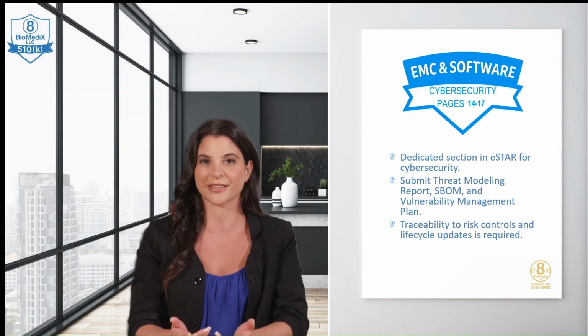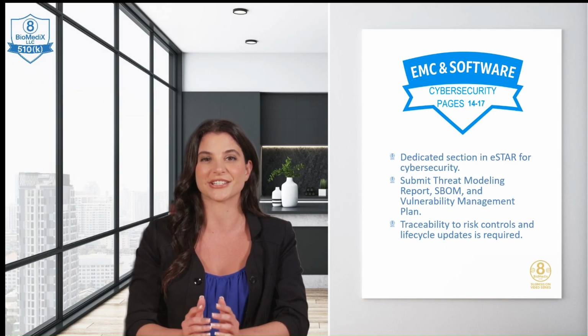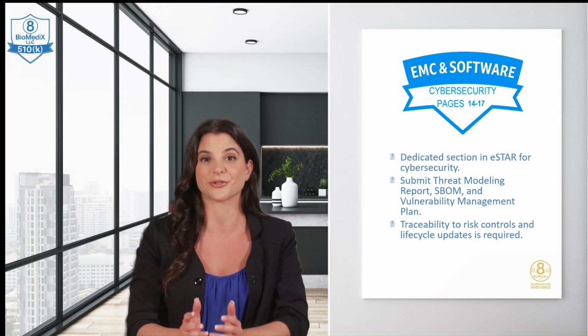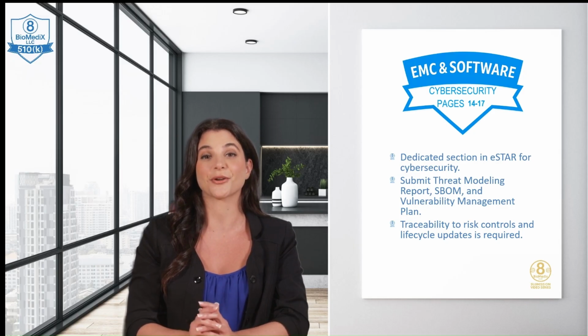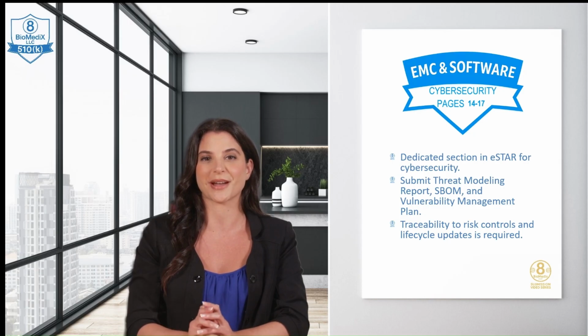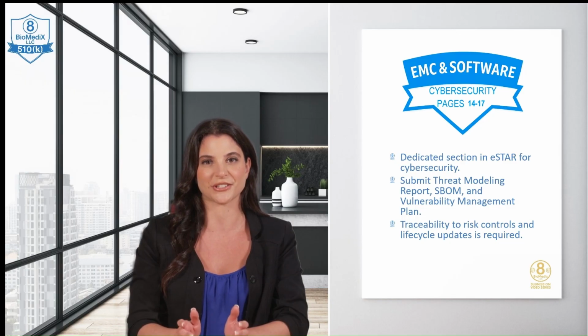Building on that foundation, cybersecurity now has its own section in eSTAR, pages 14 to 17. Why? Because cyber threats are dynamic, widespread, and pose serious risks to patient safety. You'll be asked to upload a threat modeling report showing how you identified vulnerabilities and what controls are in place to mitigate them. A software bill of materials, SBOM, listing all code elements, including third-party and open-source components. A vulnerability management plan, detailing how you'll monitor, assess, and respond to new threats over time.